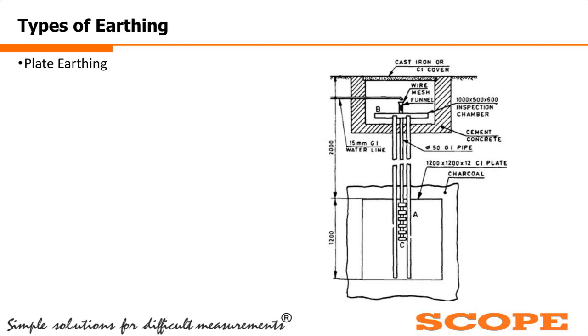Now we will see the different types of earthings. The first one is plate earthing, in which certain depths are predefined. In this type of plate earthing, generally copper plates are used for earthing purposes. Charcoal, or nowadays special chemical compounds, are used to increase the reliability of this type of earthing. These charcoal and other compounds effectively reduce the grounding resistance. So this is the first type, which is plate earthing.